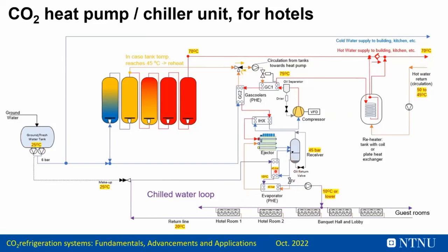And we apply a two-stage evaporation here. One evaporator is on a gravity-fed loop, self-circulation, which is around 45 bar, meaning 10 degrees C. While the other evaporator is 5 Kelvin lower, 5 bar lower, because the suction of the ejector is able to reduce the pressure on the suction side of this evaporator and makes it possible to go 5 Kelvin lower, so we can achieve maybe 5 degrees C at 40 bar.